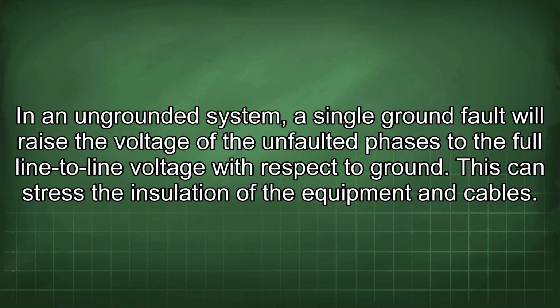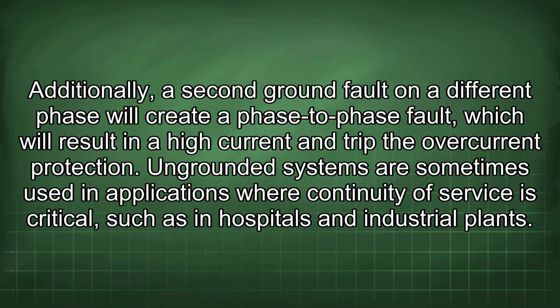In an ungrounded system, a single ground fault will raise the voltage of the unfaulted phases to the full line-to-line voltage with respect to ground. This can stress the insulation of the equipment and cables. Additionally, a second ground fault on a different phase will create a phase-to-phase fault, which will result in a high current and trip the overcurrent protection.